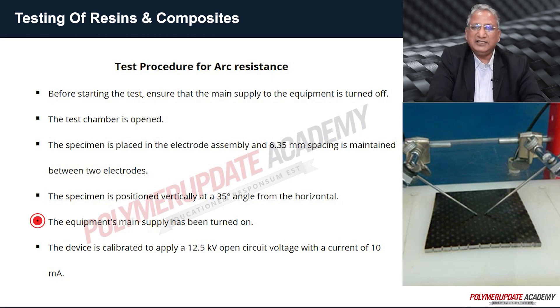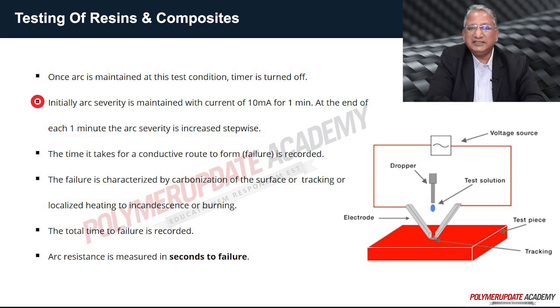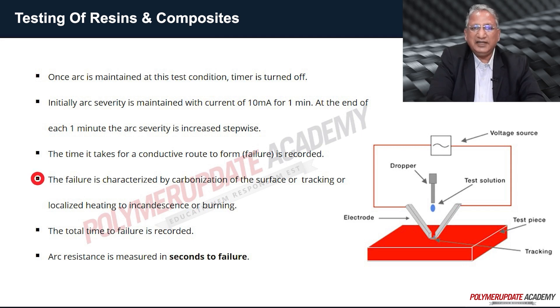The main supply of equipment is switched on. The equipment is calibrated to apply an open circuit voltage of 12.5 kilovolts and the current is adjusted to 10 milliamperes. Once the arc is maintained at this test condition, the timer is started. Initially, arc severity is maintained at 10 milliamperes for one minute, then increased stepwise at the end of each minute. The time for formation of a conductive path (failure) is recorded. Failure is characterized by carbonization of the surface, tracking, localized heating to incandescence, or burning. Total time to failure is recorded, and arc resistance is measured in seconds.